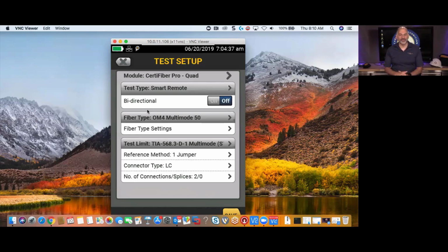If we don't select the right fiber type, then the applications that we're going to get on our report are not going to accurately reflect what that fiber is capable of. And the customer may come back and say, hey, look, you told me we could run this particular technology across there, and it says on the report you can't. You don't want that to happen. So going in and setting up these parameters properly at the beginning is critical. And this is why, just to reiterate, in that CCTT training, this is what we spend an entire day on with the fiber, going through and talking about what settings are out there, why those settings are so important, and what they can impact.